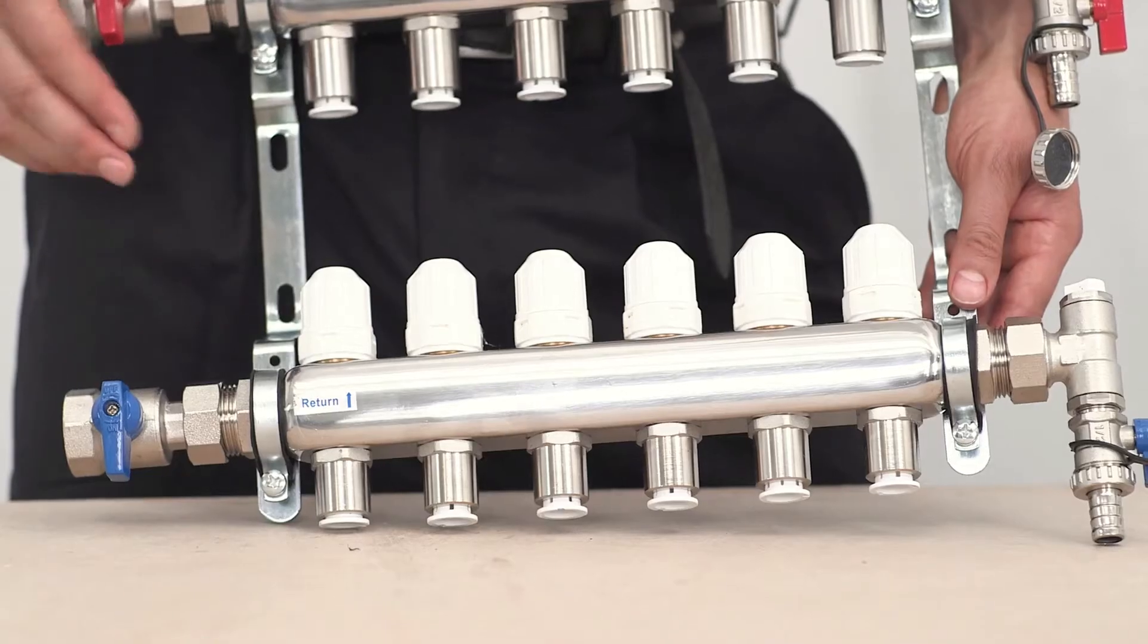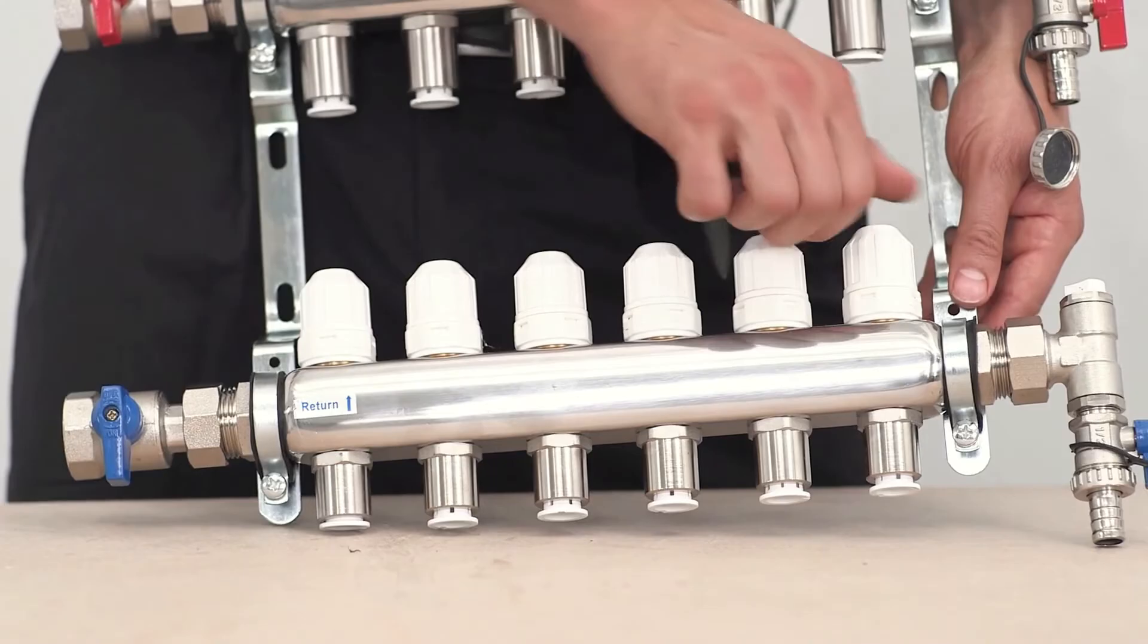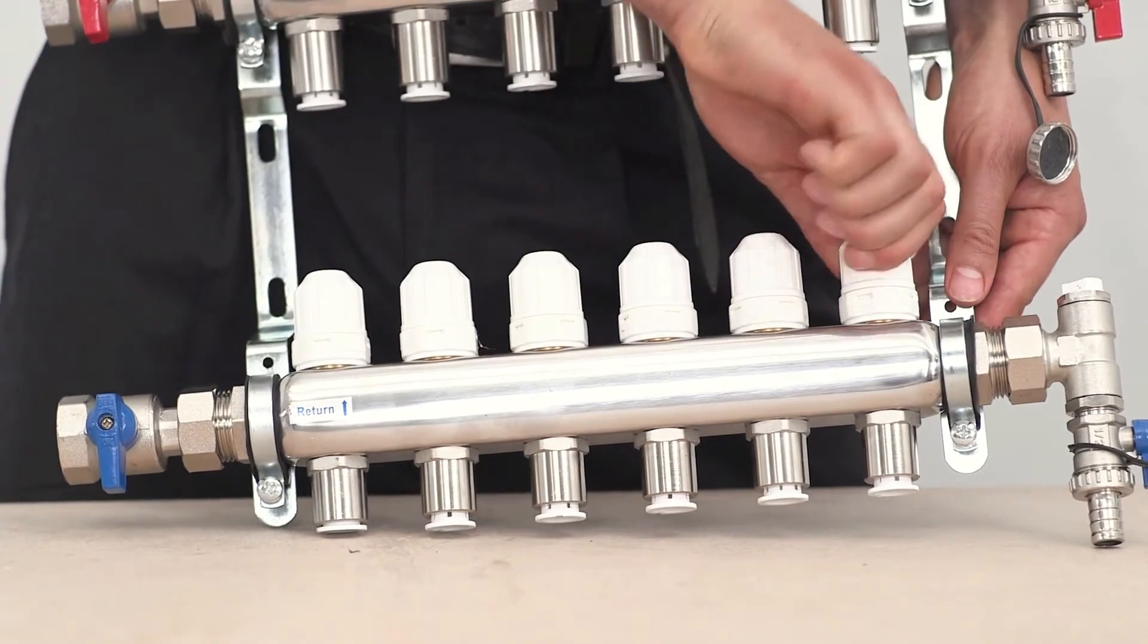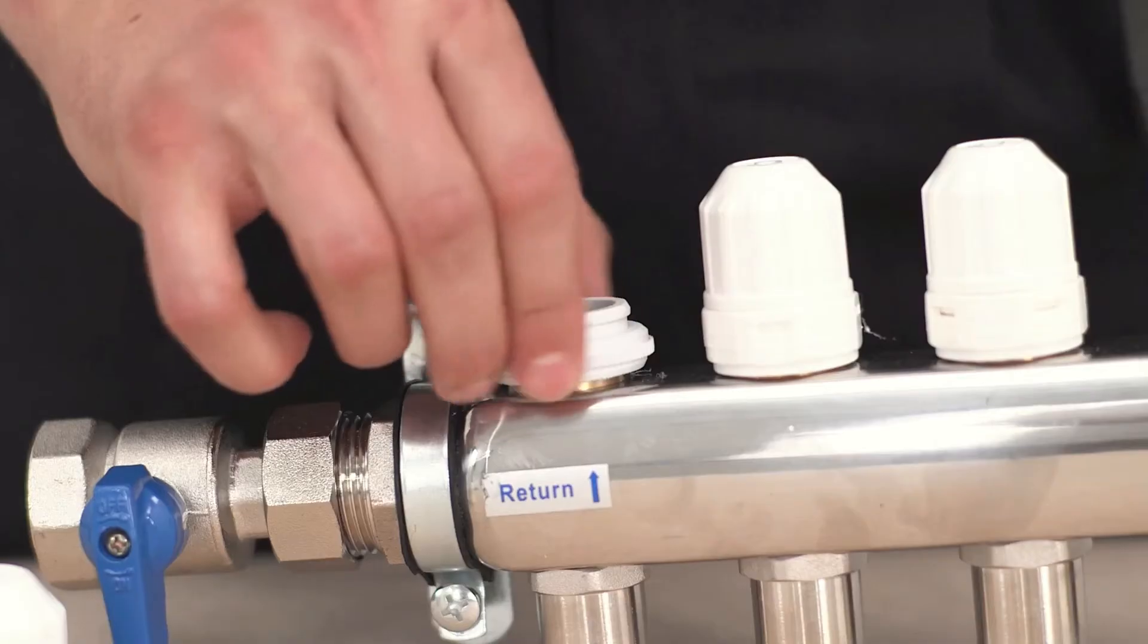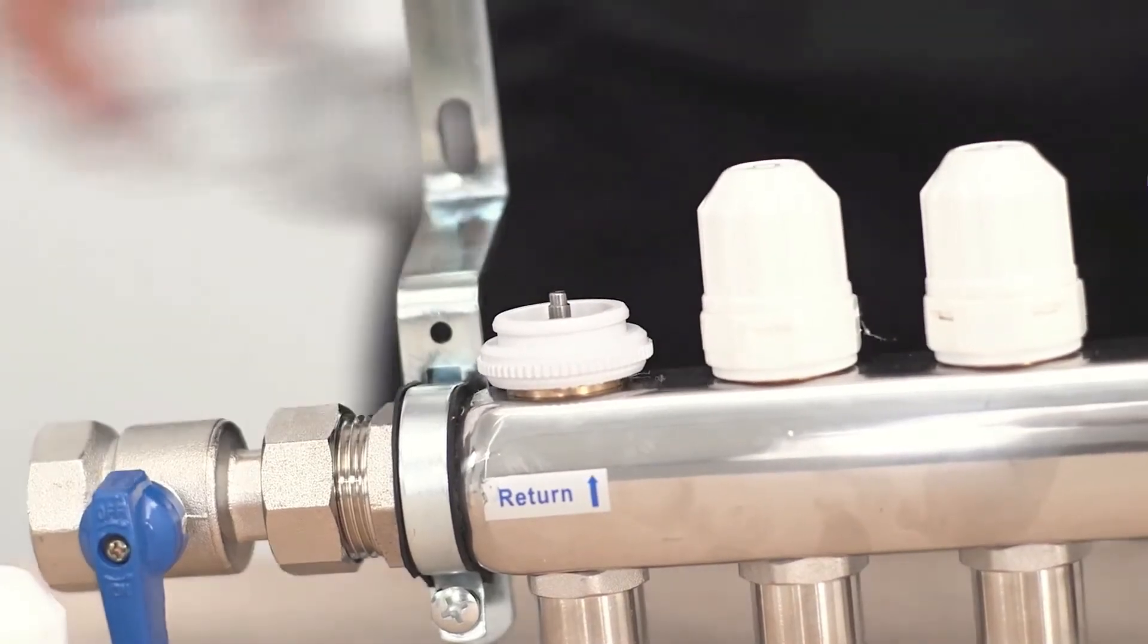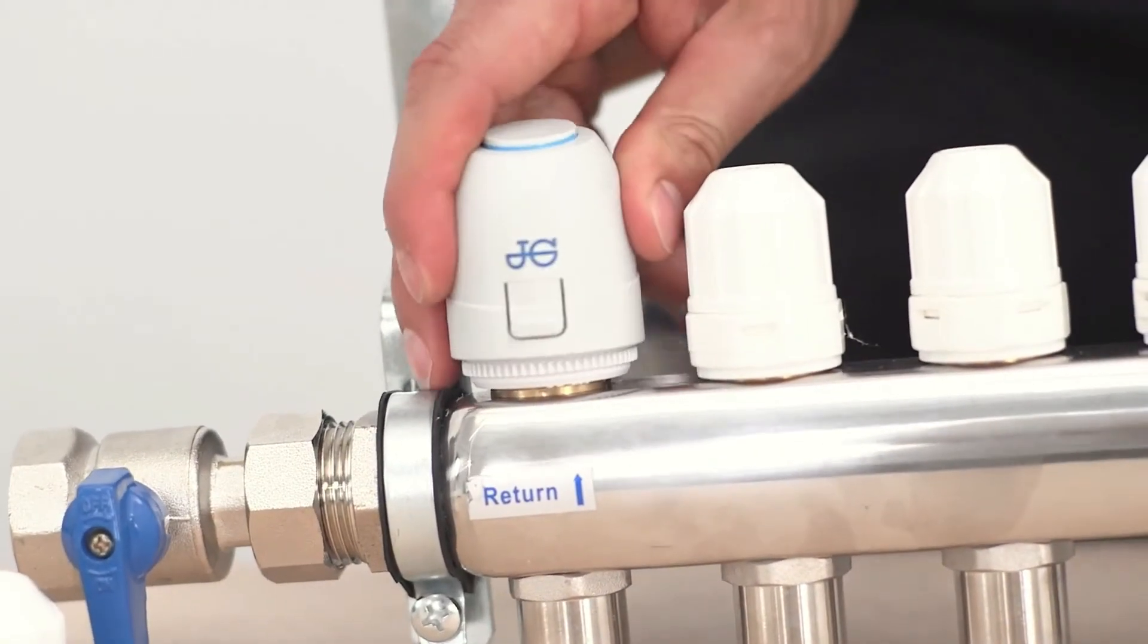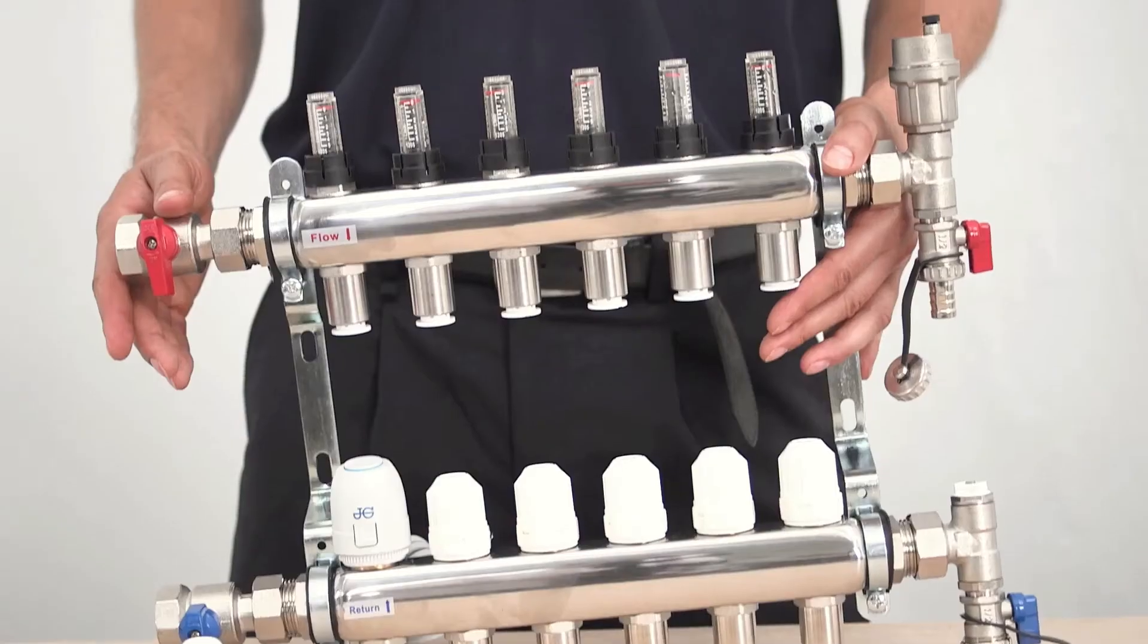We have temporary decorators caps on the bottom rail. These are used for isolation and adjustments of the circuits and will be replaced by electrically operated actuators at the commissioning stage. The actuators allow the user to control each room individually.